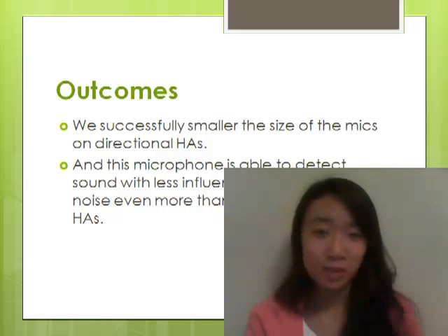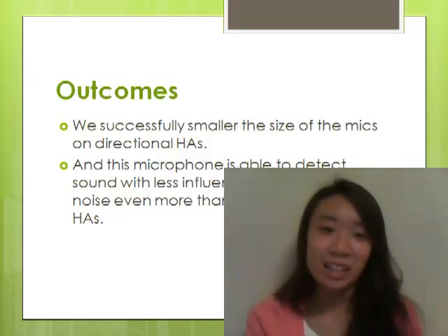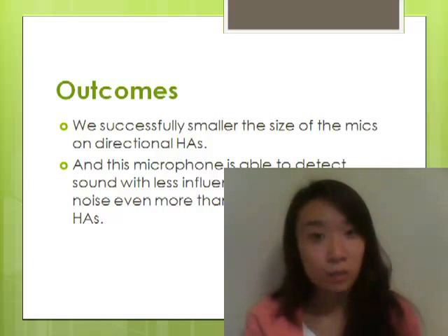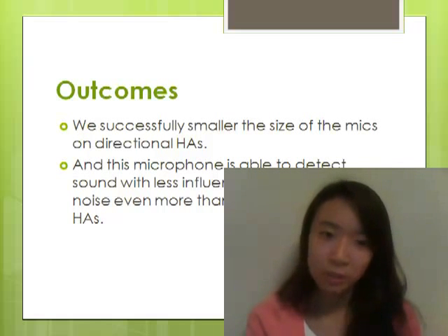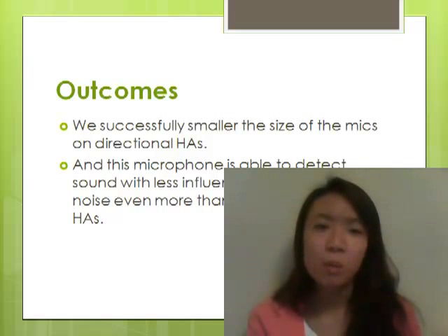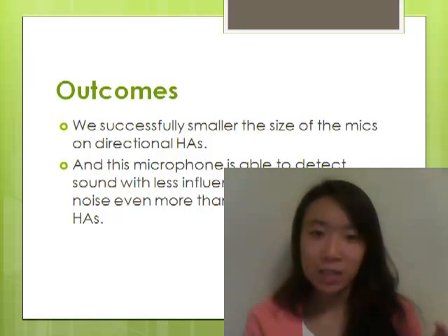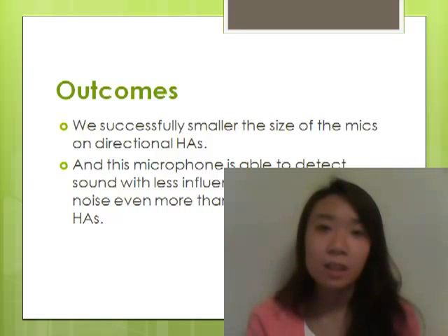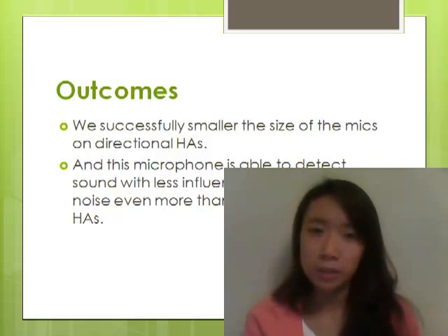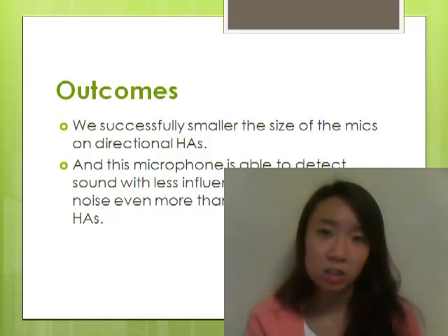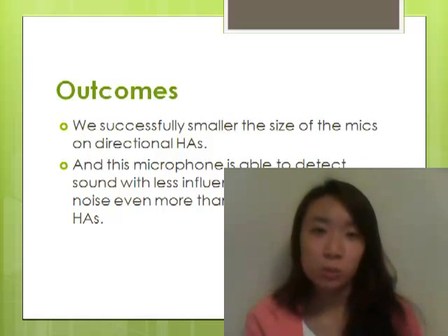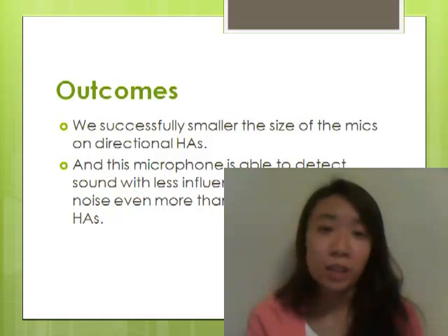So we successfully applied this finding on the fly to our hearing aid directional microphone technology, and the outcome is very successful. We successfully reduced the size of the microphones on directional hearing aids, and this microphone is also able to detect sound with less influence from internal microphone noise, which is even more successful than the existing low-noise microphone hearing aids. So I am very excited and looking forward to seeing more applications of this new technology on directional microphones, which will contribute to our hearing aids more and more in the future.